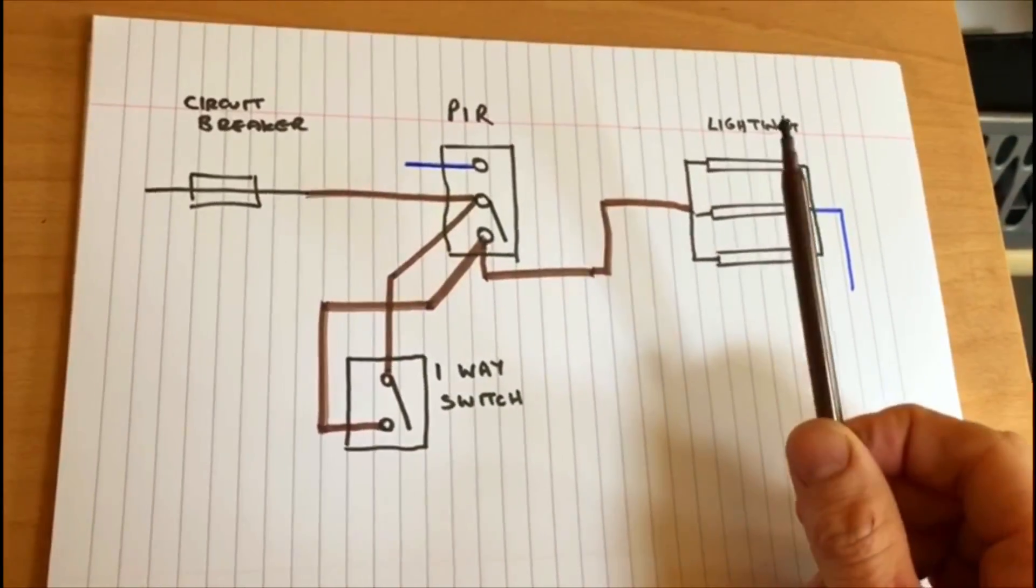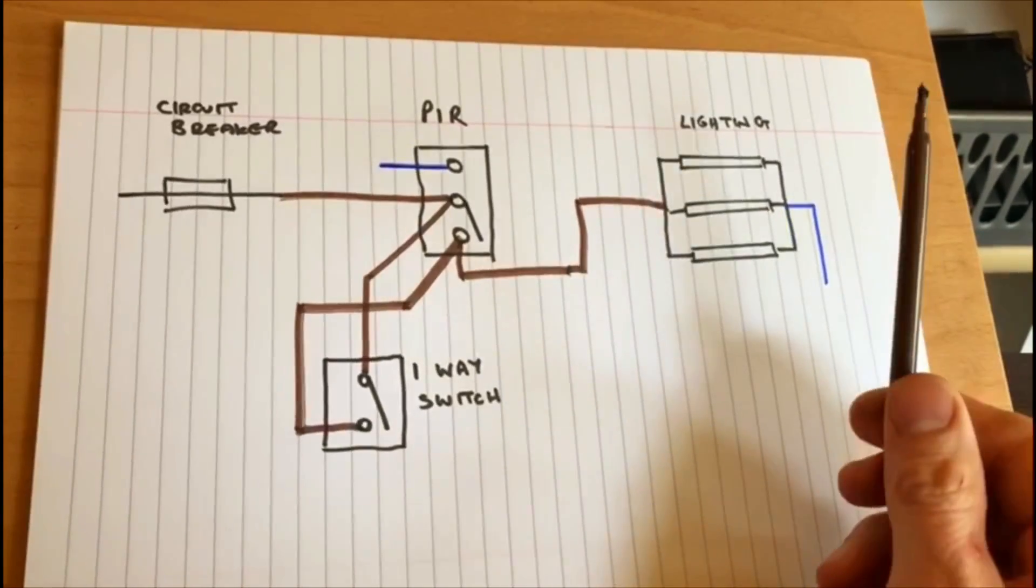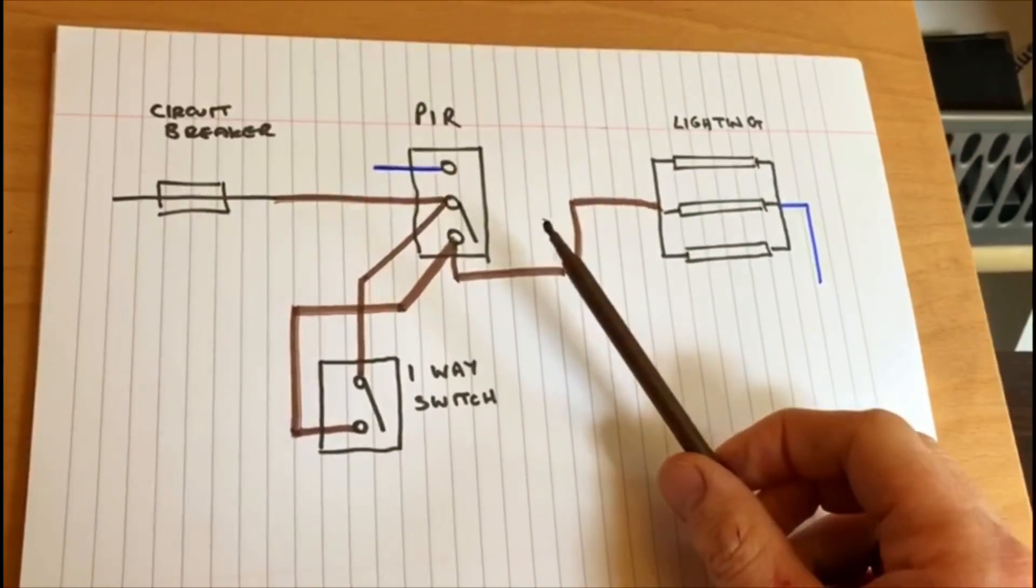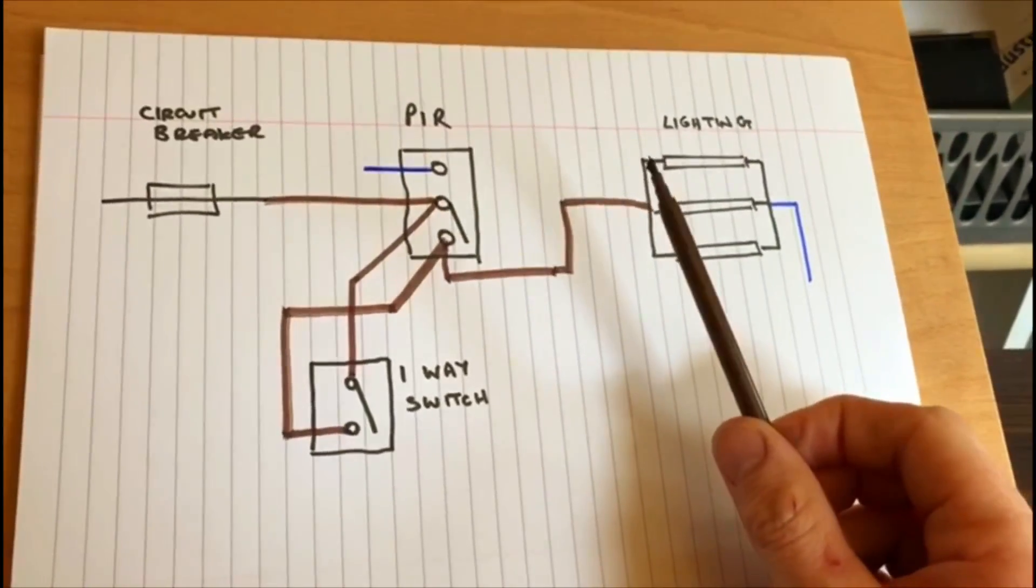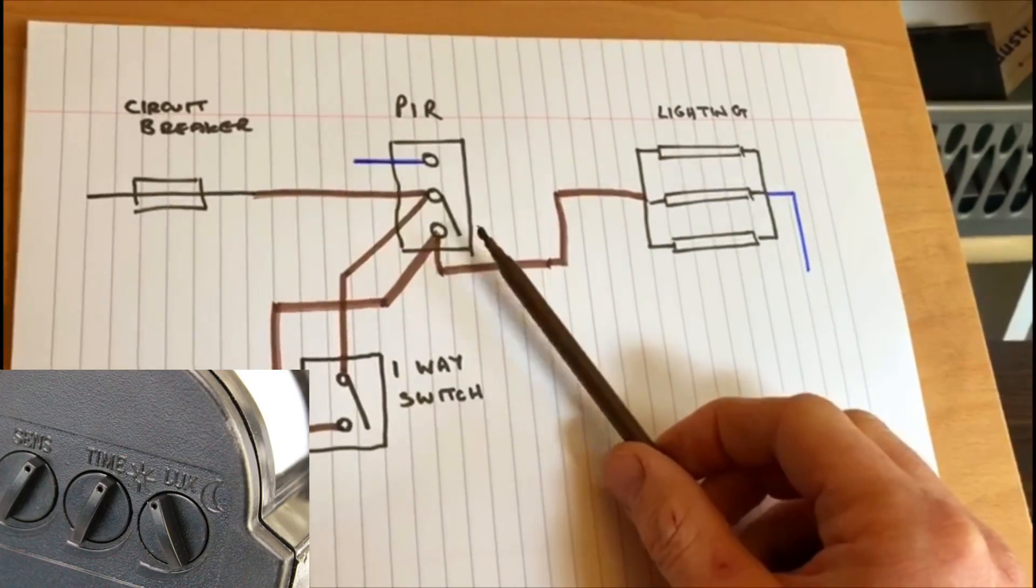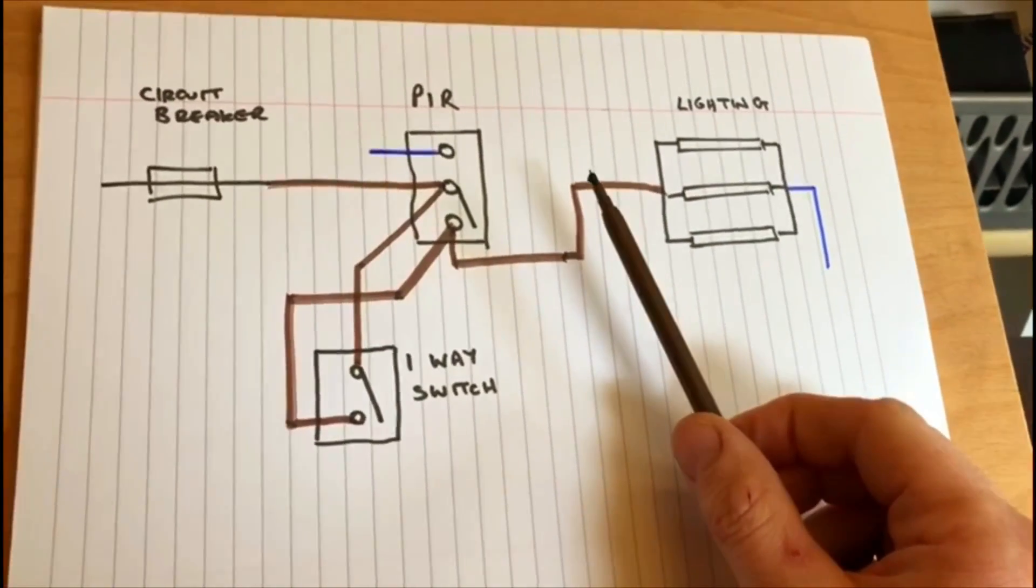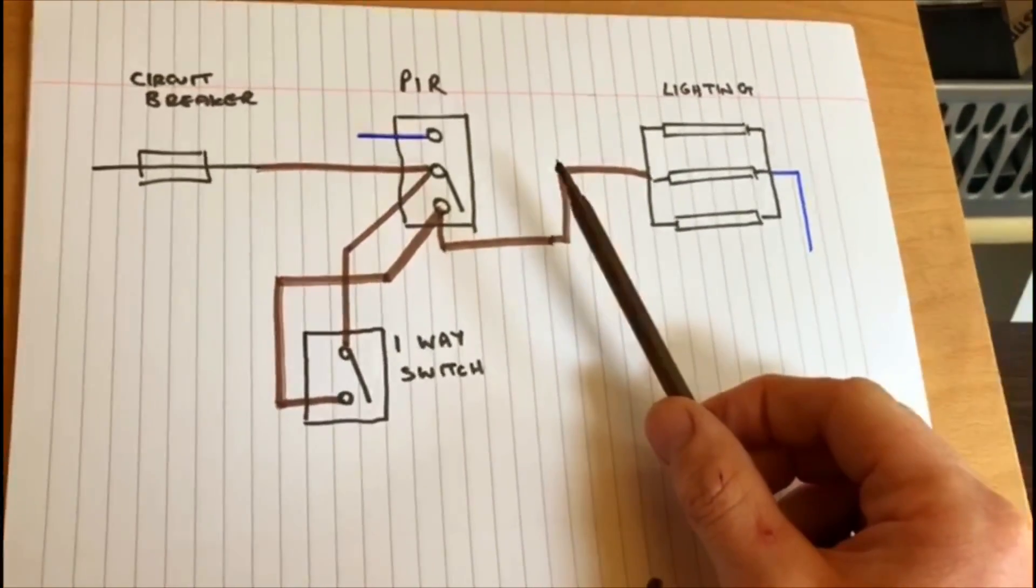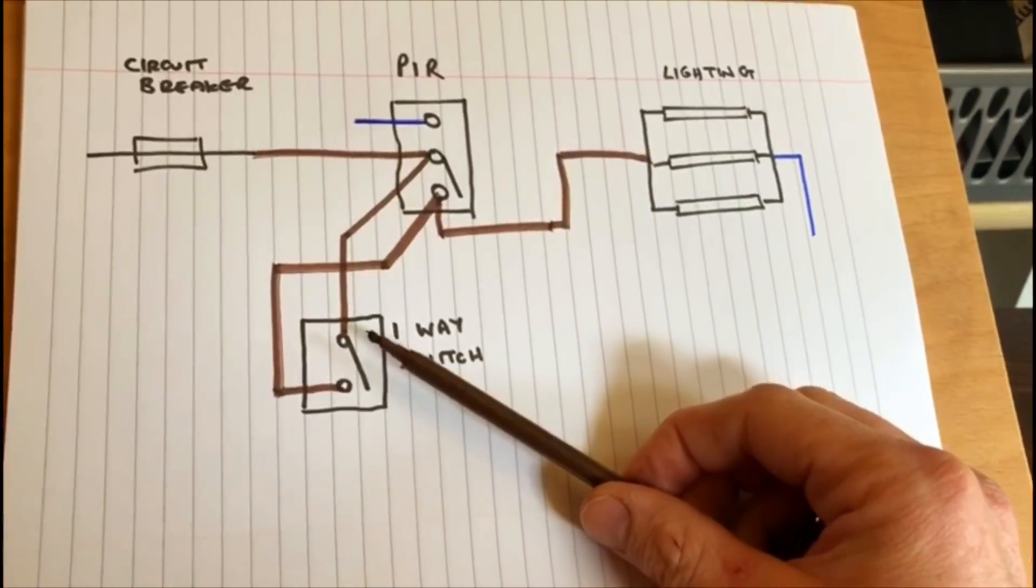Now the only issue is if the PIR has only been set to operate for say maybe 10 seconds, and you've got this in a situation where you might want to be in the place for more than 10 seconds, you can do one of two things. You can either adjust the PIR to last longer, or you can install a manual override switch. And all this is is just a one-way switch. So as you can see now...